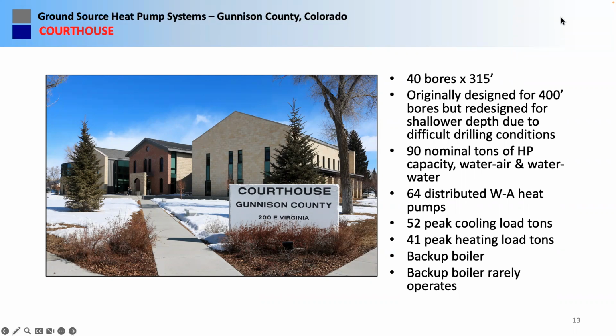By the way, that's controlled so that if the ground loop were ever to get too cold, the boiler tempers the supply water temperature to the heat pumps. If it's a condensing boiler, and you're only having to maintain like 35 degrees to the heat pumps, you're going to get the peak efficiency out of that boiler. So using the attributes of a ground source heat pump system, you can optimize even the backup boiler for a system like this. As John said, it doesn't need it — he just has to exercise it occasionally so it doesn't go bad.